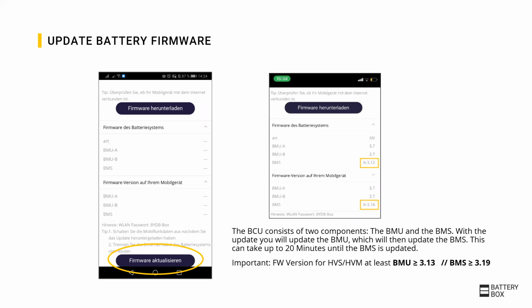When you are connected, update the firmware to the battery. You will see the version in the app and on the battery. For the update, it is important to know that the BCU consists of 2 components, the BMU and the BMS. With the update, you will update automatically and instantly the BMU, which will then update the BMS. This can take up to 20 minutes until the BMS is updated, but you can already continue with the configuration. The firmware version of the battery box, HVS or HVM, needs to be at least BMU version 3.13 and BMS version 3.19.